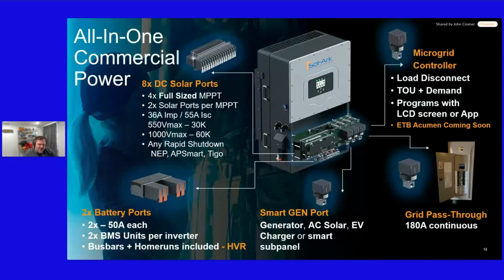Looking at the GEN port, if you have 3-phase generators, that's another area where this system is ahead. We have a 208 volt 3-phase generator input or a 480 volt 3-phase generator input, depending on whether you're using the 30K 208 or the 60K 480. So it's very easy to integrate generators and very easy to integrate AC solar.